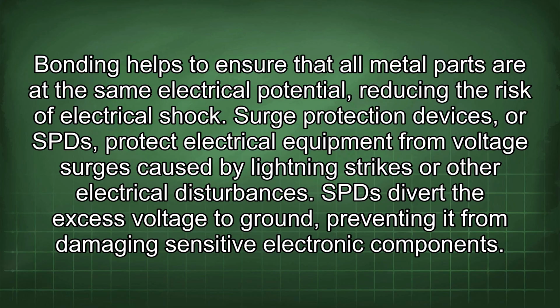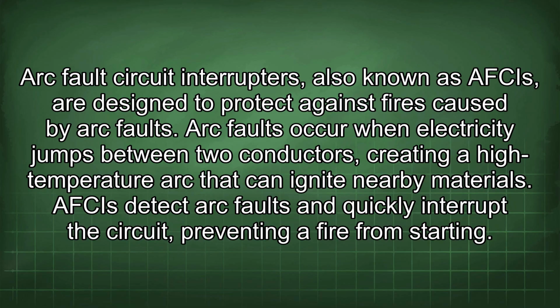Surge protection devices, or SPDs, protect electrical equipment from voltage surges caused by lightning strikes or other electrical disturbances. SPDs divert the excess voltage to ground, preventing it from damaging sensitive electronic components. Arc fault circuit interrupters, also known as AFCIs, are designed to protect against fires caused by arc faults. Arc faults occur when electricity jumps between two conductors, creating a high-temperature arc that can ignite nearby materials. AFCIs detect arc faults and quickly interrupt the circuit, preventing a fire from starting.